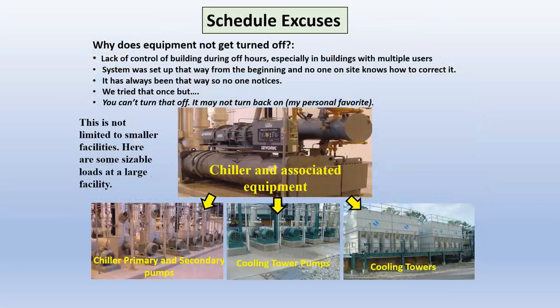So we talked about scheduling with the BAS. And I always like this slide. I throw it in a bunch of different presentations, but here are some of the things you'll hear on why equipment does not get turned off. Lack of control of the building during the off hours, especially in buildings with multiple users. The system was set up that way from the beginning. Nobody really knows how to correct it. It has always been that way, so no one notices. That's sad but true. We tried that once, and then my favorite as a maintenance guy, which really hurts: you can't turn that off because we may not be able to turn it back on. If someone is saying that, then they really don't have a maintenance program.